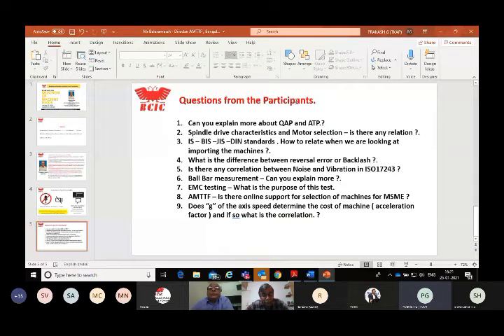The other option, if you want a direct drive and yet want power at a lower speed, is to ask for a special motor, which is available nowadays. Motors are available not only at 1500 base speed, but also below that, at 750 or 500. The cost goes up, but yes, solutions are available.